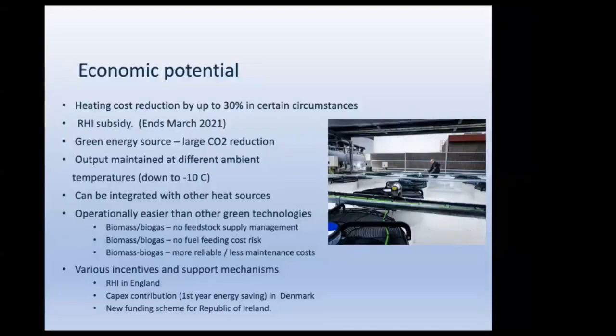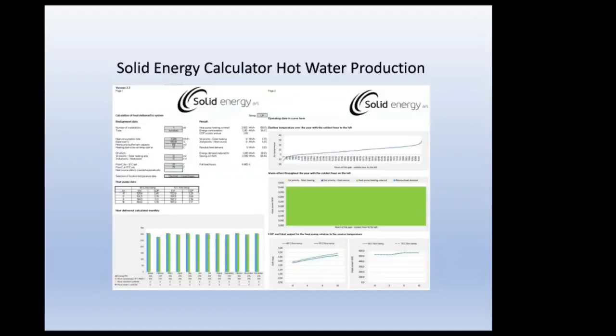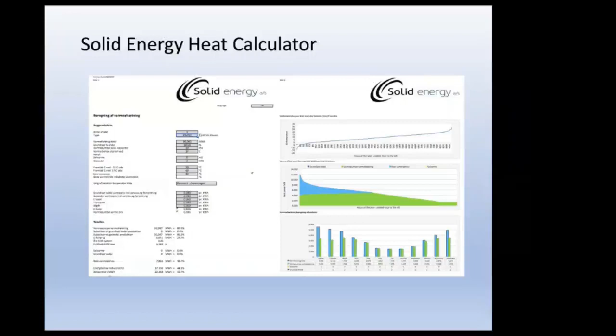If you want to go into the technical details of sizing a heat pump, I can let you have a calculator which helps put the flow and return in, the heat demand, and it will give you numbers as to what heat pump you actually require. On the graph on the right, the blue section is actually the heat demand that is not covered by a heat pump. That's a bivalent system, whereby the green is the heat pump input and the blue would be the existing gas or oil boilers.